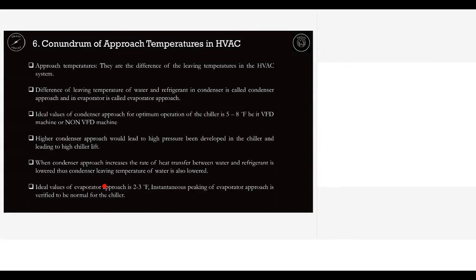As I mentioned, the condenser approach and approach temperatures apply to any heat exchanger facilitating heat exchange from a source to a sink, which is subject to scaling if water is involved. So water quality is a factor and a problem. If water quality is bad, scales adhere to the heat exchanger surface, decreasing the efficiency of the system. In a chiller, this is called the condenser approach, and for academic and industrial purposes, the normal value is 5 to 8 degrees Fahrenheit. If it goes above this number, your efficiency takes a big hit. So the lesser the approach, the lesser the scaling, and the better the efficiency of the system.